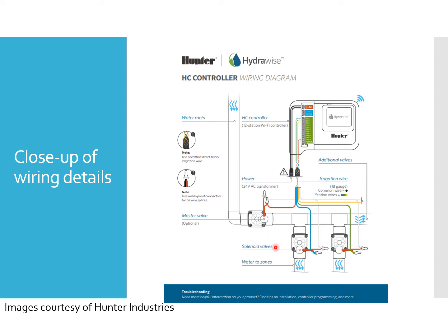Now, if you were using this in conjunction with a flow sensor, which would be plumbed in between these two with some space in between, you could wire that up to your controller and it would learn the flow of each of these valves. Then, if either one of these valves ever operated in a way that was outside of its window of accepted flow rates that you've set for it, then it would alert the controller and the controller would shut off the master valve.